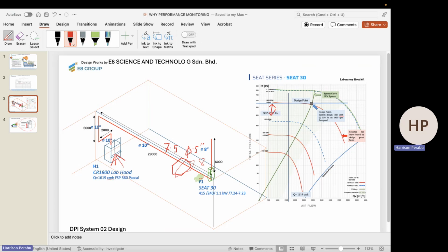Now, again, adsorption filters are not designed to capture aerosols. So the allowable pressure loss for this is usually kept very low, because its function is not to capture dust. Which means that if it gets clogged, if the differential pressure goes up, that means we have to clean the filter. Why is an adsorption filter going to get clogged? Mainly because it's designed to capture gases and vapor, not aerosols. If the room air has dust.